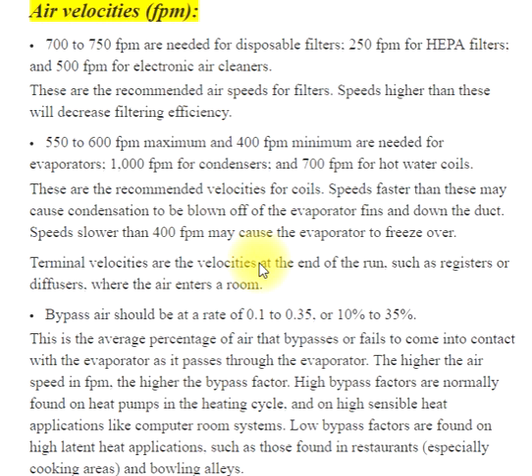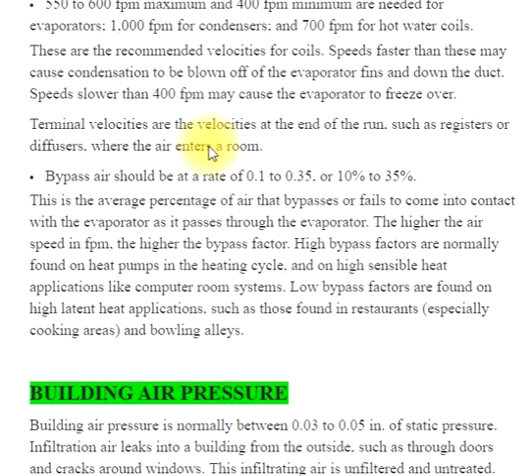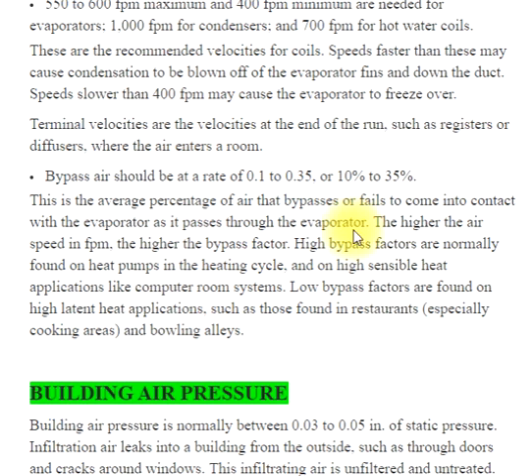Terminal velocities are the velocities at the end of the run, such as registers or diffusers, where the air enters a room. Bypass air should be at a rate of 0.1 to 0.35, or 10% to 35%. This is the average percentage of air that bypasses or fails to come into contact with the evaporator as it passes through. The higher the airspeed in FPM, the higher the bypass factor.